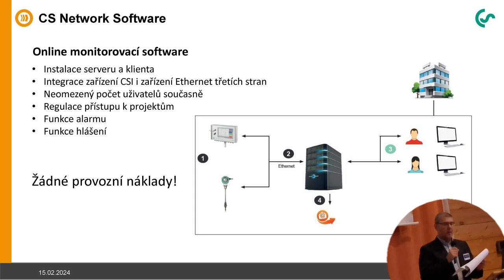So we have an alarming function, sending out emails, we have a reporting function, the software will automatically send a report, who needs how much compressed air per week, per month, per year, and so on. And the big advantage with this software, you have no running costs. You don't have to pay a monthly fee. You buy the software once, and then you can use it over the years.